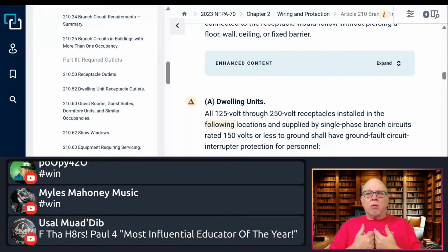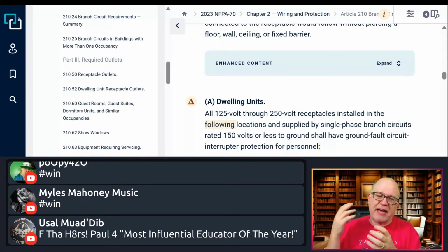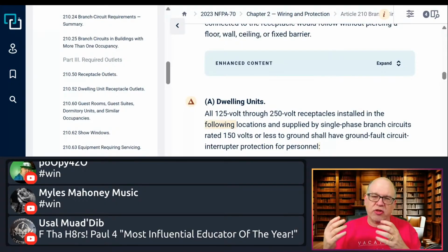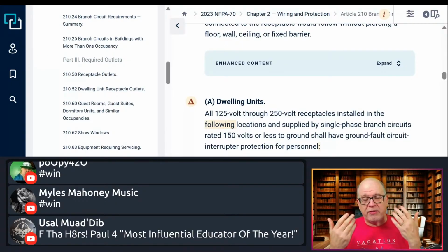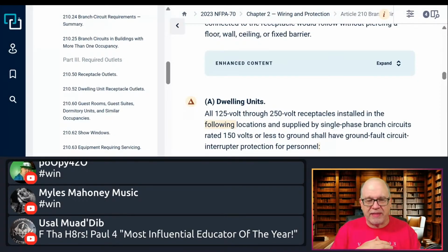So when we're talking about consistency, for example, if you're dealing with a multi-wire branch circuit in a commercial application, you want to make sure that you splice all of your neutrals together and then take a pigtail jumper over to the device, so that removing the device does not turn two multi-wire branch circuits into one line-to-line 240 volt circuit, and now you're going to burn things up.